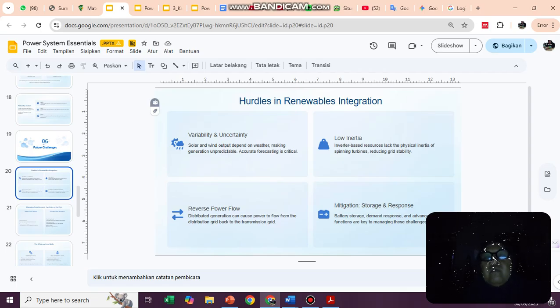And then future challenge, hurdles in renewables integration. Variability and uncertainty: solar and wind output depend on weather, making generation unpredictable. Accurate forecasting is critical. And then low inertia. Inverter-based resources lack the physical inertia of spinning turbines, reducing grid stability. And then reverse power flow. Distributed generation can cause power to flow from the distribution grid back to the transmission grid.